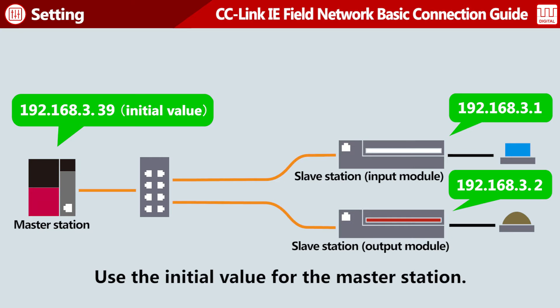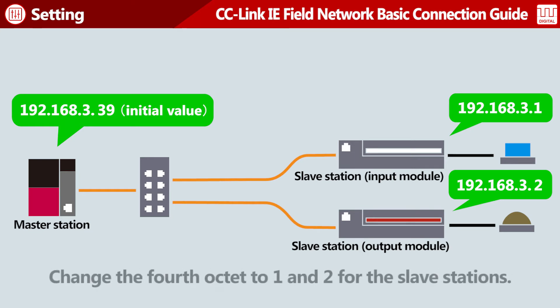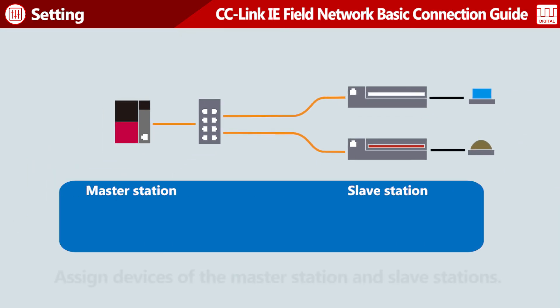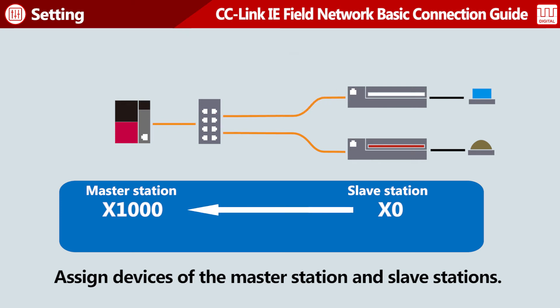Set the IP address initial value shown here to the master station. Change the fourth octet of the IP address set to the master station to 1 and 2, and set them to the slave stations. Assign devices of the master station and slave stations to exchange I/O signals.